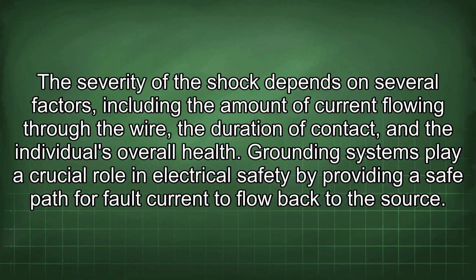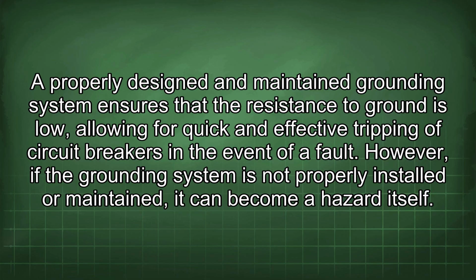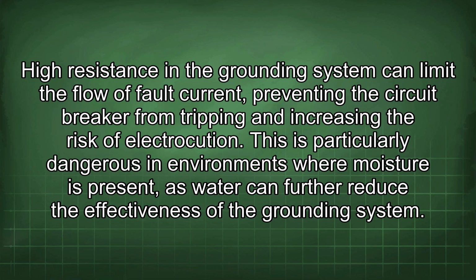Grounding systems play a crucial role in electrical safety by providing a safe path for fault current to flow back to the source. A properly designed and maintained grounding system ensures that the resistance to ground is lower, allowing for quick and effective tripping of circuit breakers in the event of a fault. However, if the grounding system is not properly installed or maintained, it can become a hazard itself. High resistance in the grounding system can limit the flow of fault current, preventing the circuit breaker from tripping and increasing the risk of electrocution. This is particularly dangerous in environments where moisture is present, as water can further reduce the effectiveness of the grounding system.